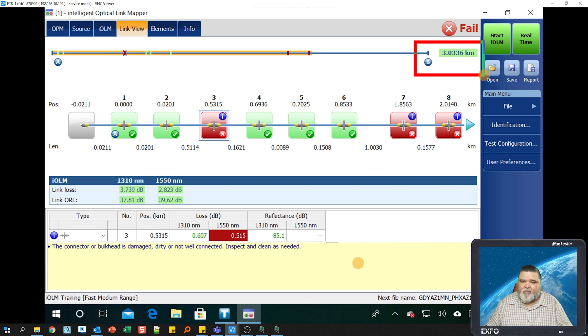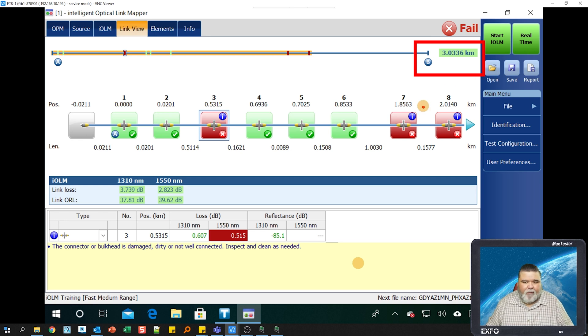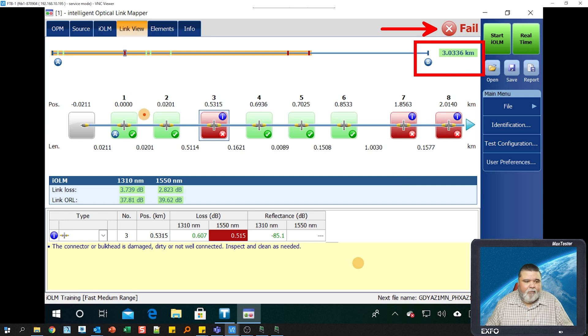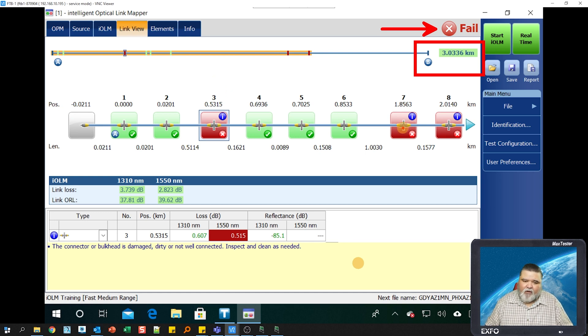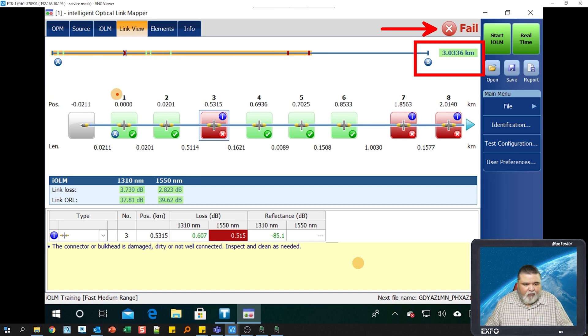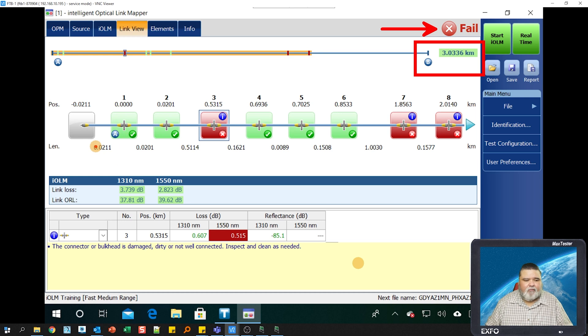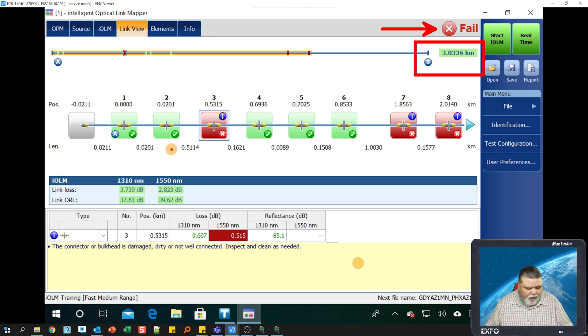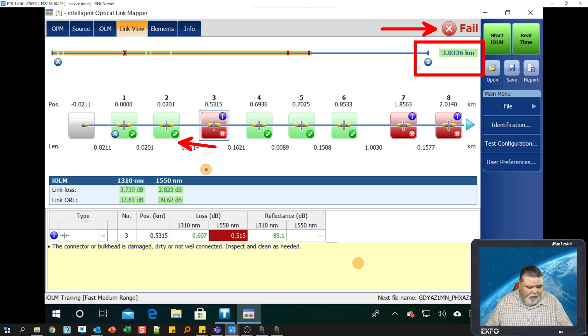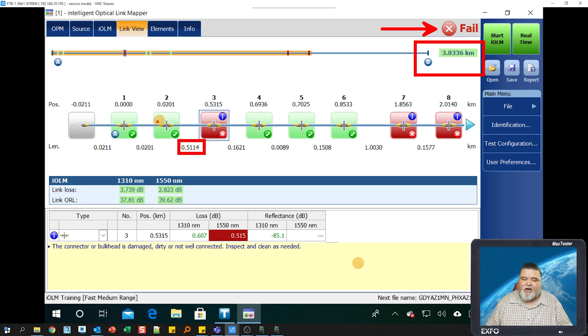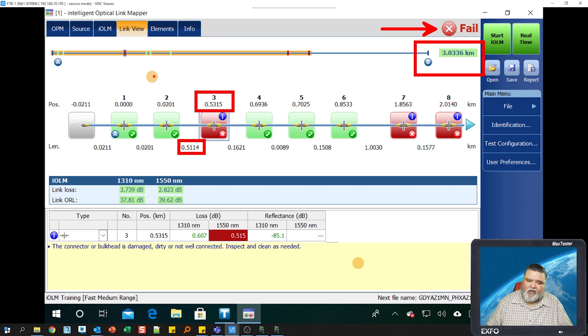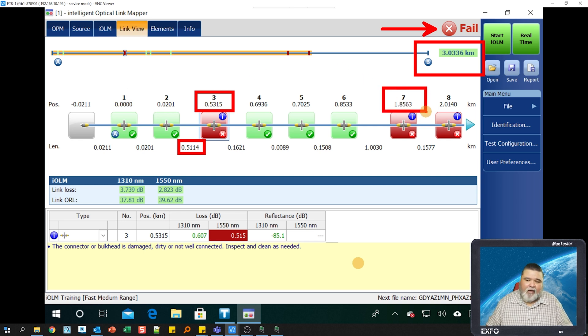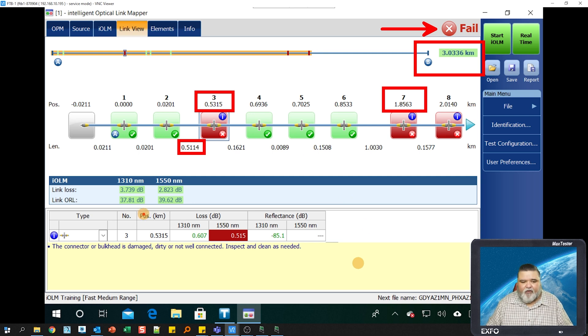Once it's complete, we start seeing some test results. You'll notice the makeup of the screen itself. We have the distance, total distance, just a little over three kilometers. Obviously we have a global pass fail here, so there's a fail somewhere. This is the link view. If you select any one of these icons, it'll jump to that icon on the network map down here. This is the end of the launch cable. I have a 20 meter launch cable, then there's another 20 meters, another connection, another 511 meters. This is the distance between these two events, 511 meters apart.